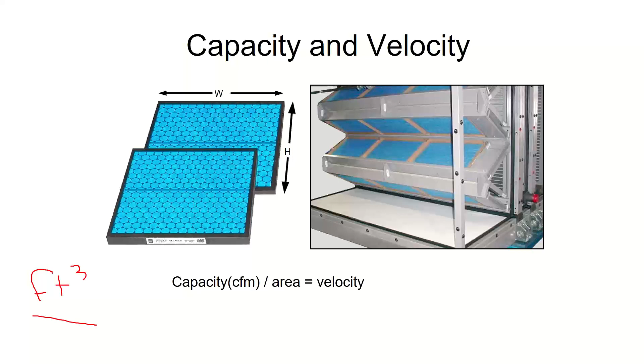My CFM isn't going to change. I suck a certain amount of airflow into the air handler. A certain amount of airflow is going to go out of the air handler. Unless my air handler is leaky, that's what's going to happen. So that's fixed. So if I want to slow down the air, and I definitely want to slow down the air, because if I have air coming through the filter at a high speed, it'll have a lot of velocity pressure. It's kind of like if you take a spitball and put it in a straw, right? You blow really hard on that, your mouth going through that straw is going to create a lot of velocity pressure. Velocity is speed plus direction.